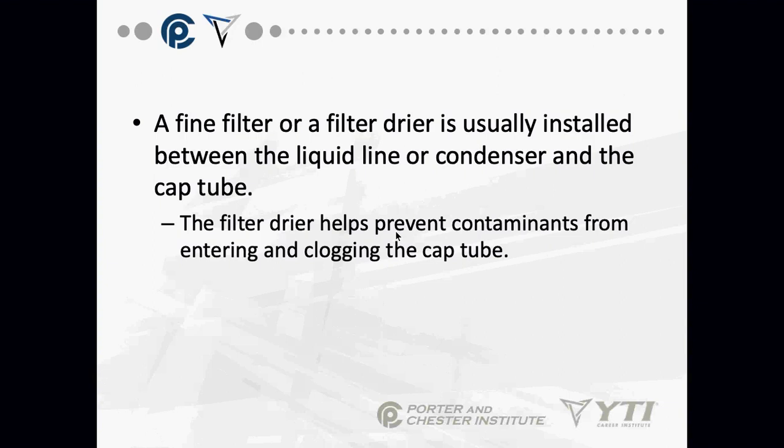Well, vacuum will remove moisture, okay? Right. Does vacuum remove hard particles? No. So when they brazed or cut the tubes? When they brazed. What about when they brazed? That is exactly where I'm going. What didn't they do when they brazed? Check for leaks. They didn't take the shards off the end of the cuts. Purge with nitrogen. What was that? That was what I was looking for. Purge with nitrogen. Purging it with nitrogen as they're brazing.